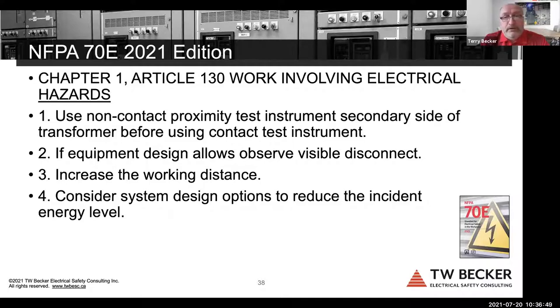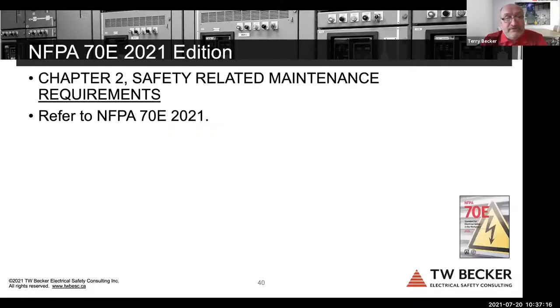So I've promoted a higher ATPV arc flash suit for quite some time. You can get a 140 cal arc flash suit from Oberon Company, a 100 cal suit from Oberon, and other vendors are moving to providing higher ATPV arc flash suits. There's a balance between engineering, incident energy reduction, and arc flash PPE. What was also added was a table that gave you the voltage class ratings of rubber insulating gloves, taken out of ASTM standards because it was never there. So this table's been added in both Z462 and 70E.